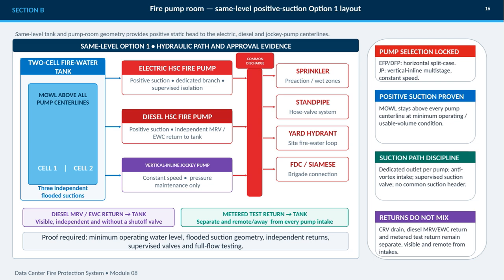Downstream, all three pumps feed a common discharge serving the sprinkler zones, standpipe hose valves, yard hydrant loop, and FDC or Siamese connection. Returns are kept separate. The diesel minimum flow and excess water return goes visibly back to the tank without a shutoff valve, while the metered test return is remote from every intake. Final approval depends on documenting the water level, flooded suction geometry, supervised valves, independent returns, and full flow testing.